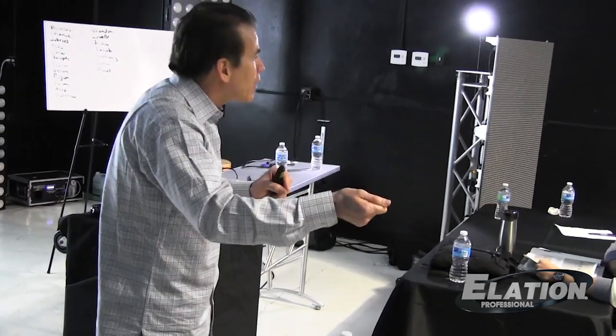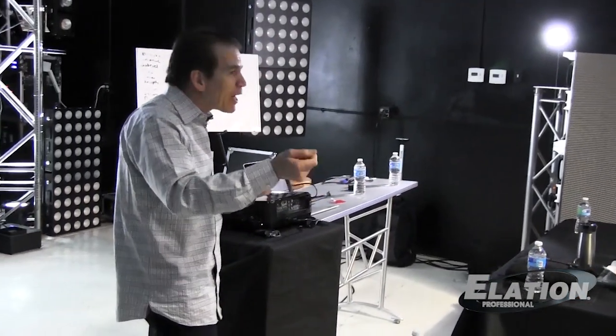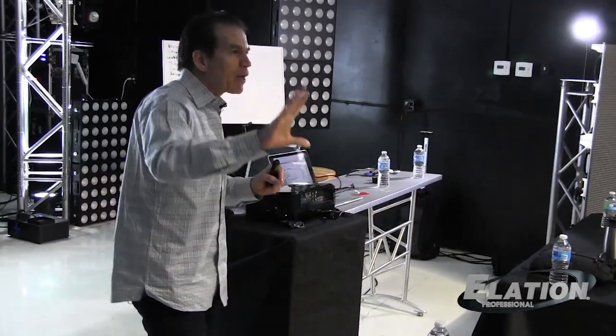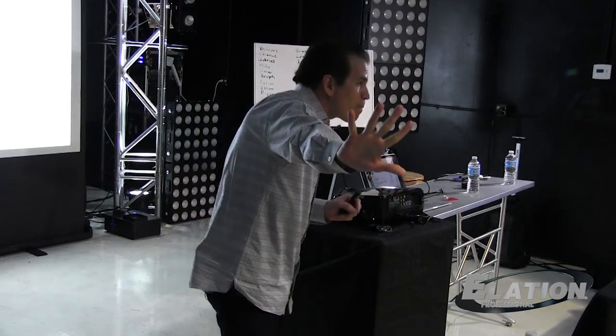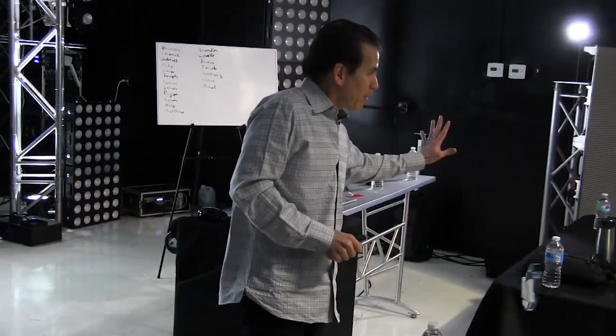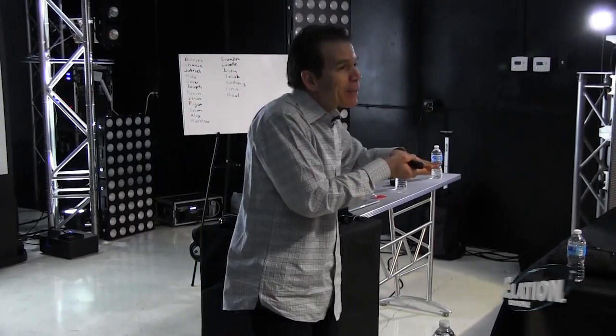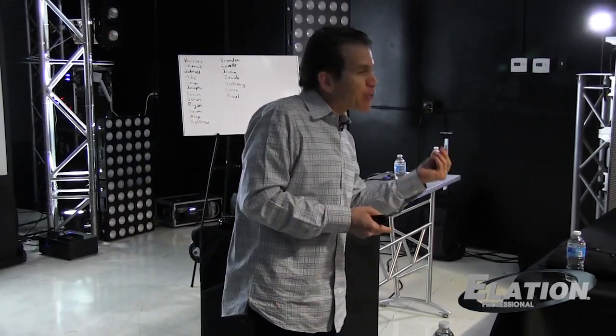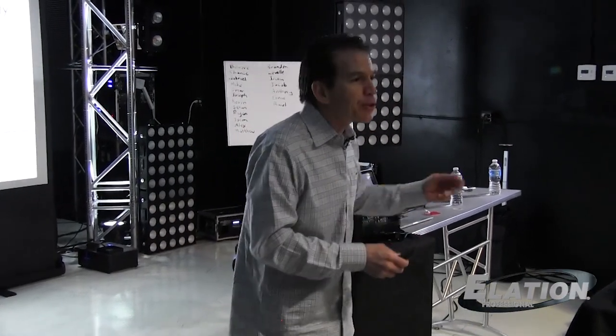The shield's plugged into the PA. The shield is connected to the chassis of the PA. The chassis of the PA is connected to that green grounding conductor. So you've got the green grounding conductor from the PA, green grounding conductor from your amplifier. And if there's a short, meaning that a hot wire, one of the black wires, the insulation breaks and leans up against the chassis, now the chassis has voltage on it, but it has nowhere to go in certain instances if there's a faulty ground. If the ground is intact, it will immediately cause the circuit breaker to trip.